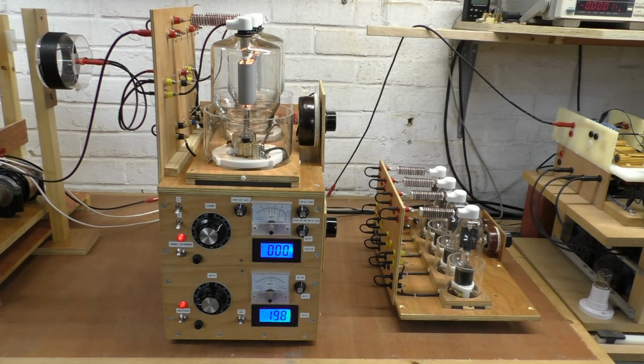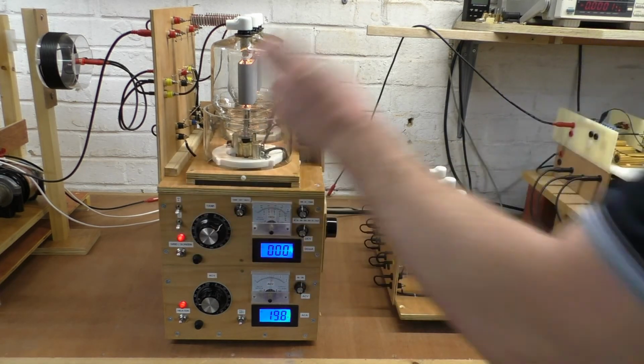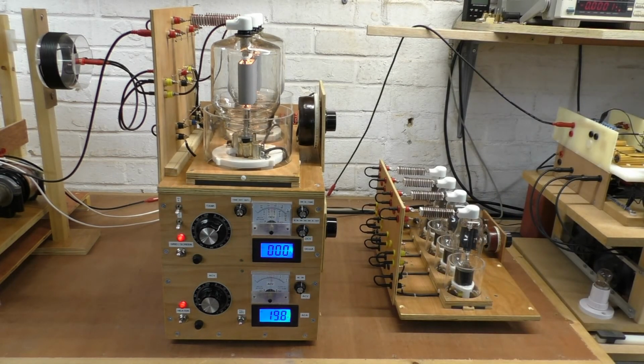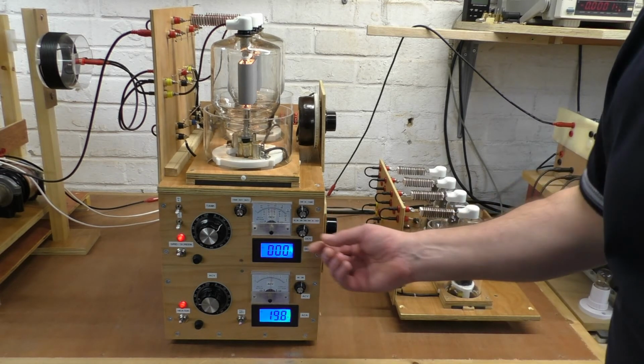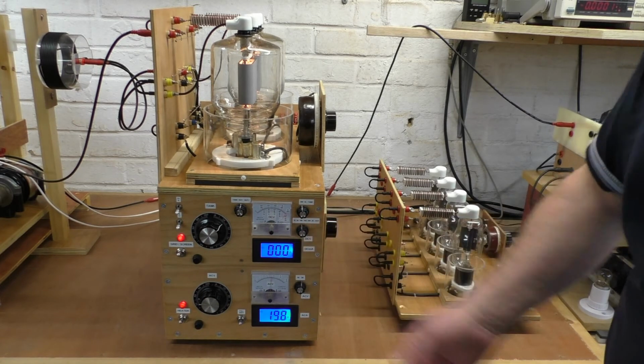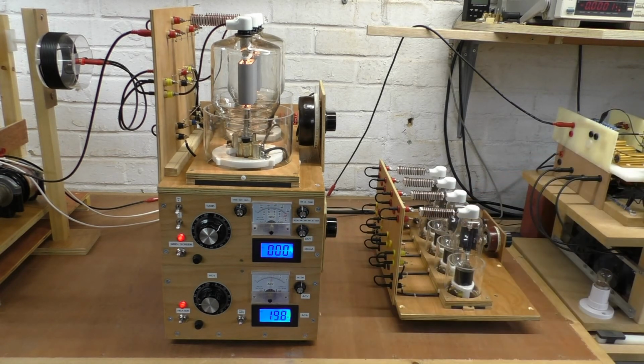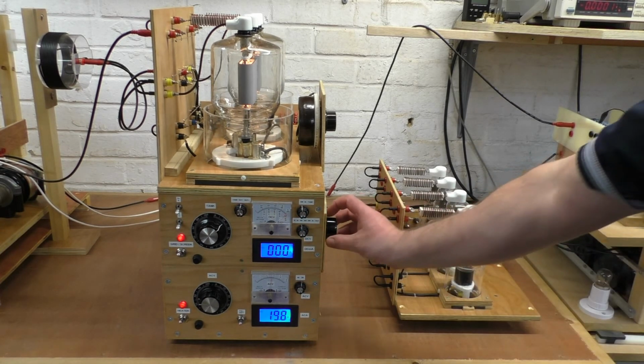So that controls the scale, the range of bias available at both ends. 200 nominally in a grid arrangement would give plus 100 and minus 100 - so plus 100 volts to minus 100 volts. We are operating on the negative side of that bias only, from 0 to minus 100. And so we'd expect 100 volts is our maximum bias, minus 100 volts.